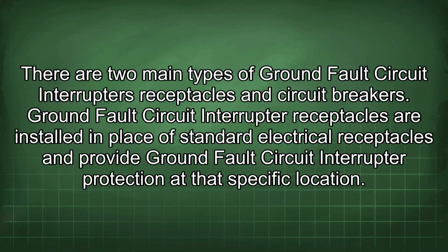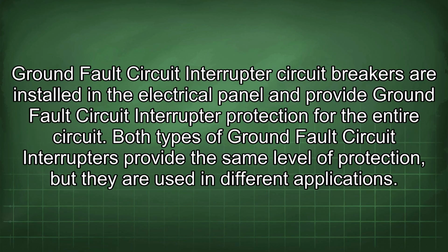There are two main types of ground fault circuit interrupters: receptacles and circuit breakers. Ground fault circuit interrupter receptacles are installed in place of standard electrical receptacles and provide ground fault circuit interrupter protection at the specific location. Ground fault circuit interrupter circuit breakers are installed in the electrical panel and provide ground fault circuit interrupter protection for the entire circuit.